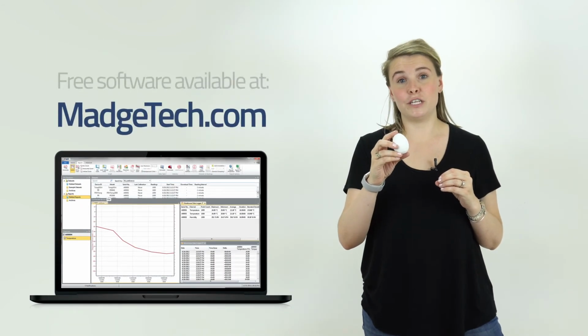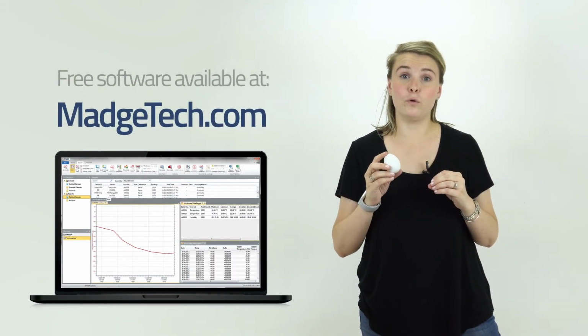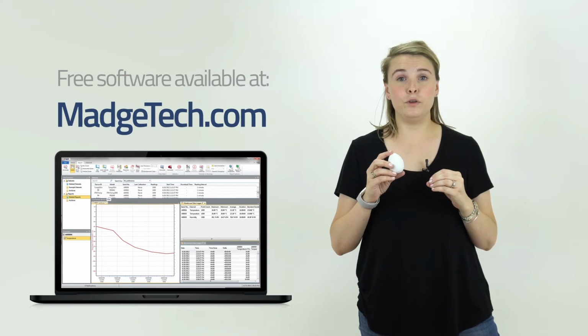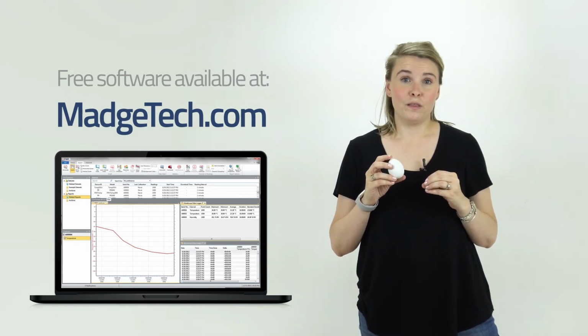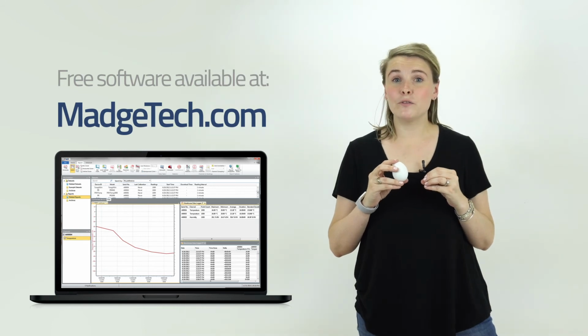Once the shipment is received, remove the MicroRHTemp and offload your data into the MadgeTech 4 software. From there, you can view all of your data in graphical, tabular, or statistical view. The MadgeTech 4 software can be easily downloaded for free from MadgeTech.com. Data reports can then be printed and filed or saved electronically for validation history.